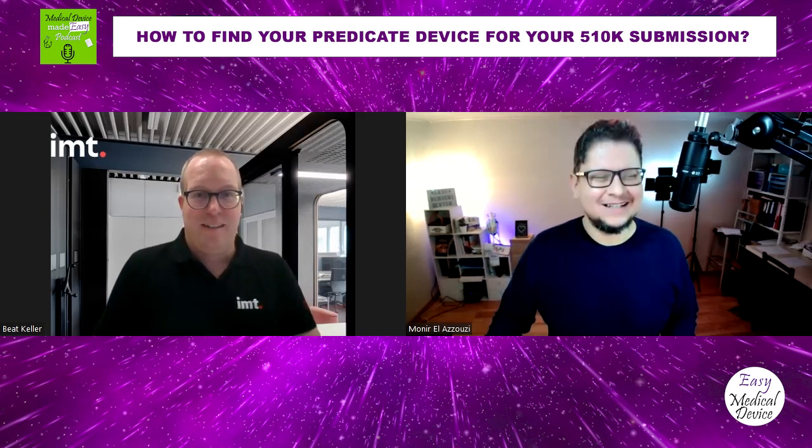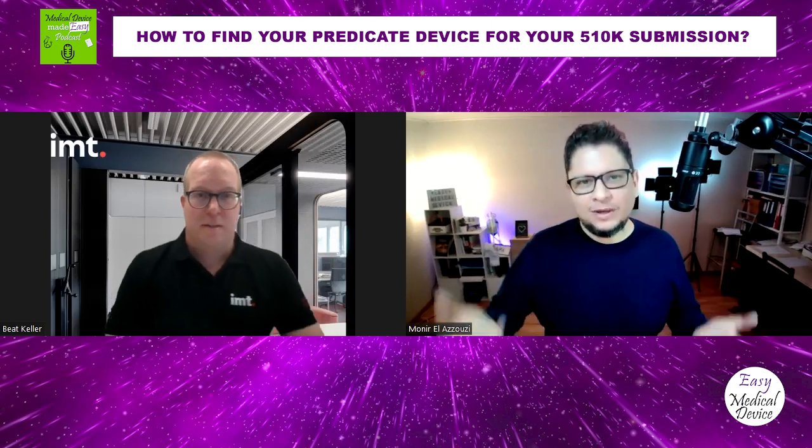Exactly. As you have some experience with the 510Ks and with those predicates, are there any common mistakes that you are always hearing, where people are always making the same mistake about predicate devices or the 510K submission, etc.? I think the biggest mistake is what we just discussed, not doing any pre-submission. Okay, just try, good luck and hope it works.